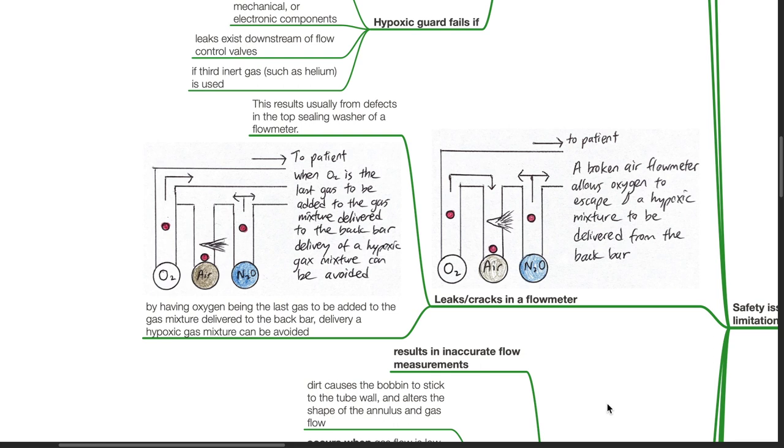Leaks or cracks in a flow meter: This results usually from defects in the top sealing washer of a flow meter. By having oxygen being the last gas to be added to the gas mixture delivered to the back bar, delivery of a hypoxic gas mixture can be avoided.